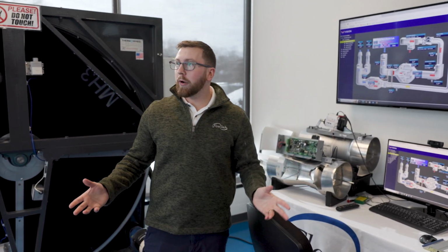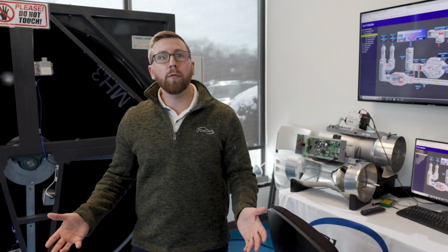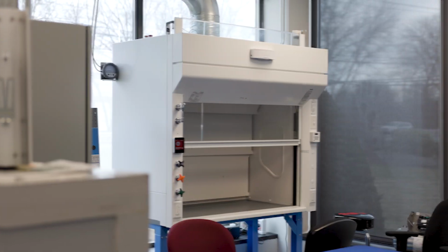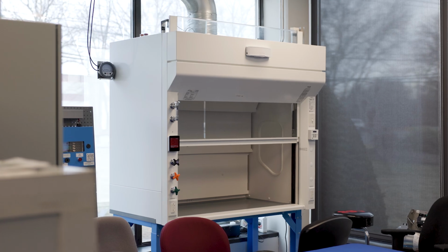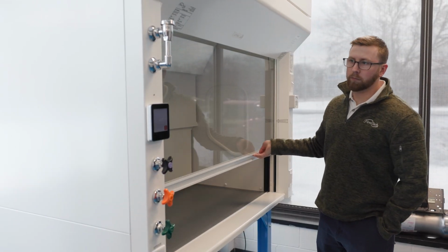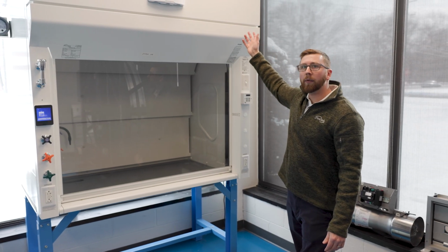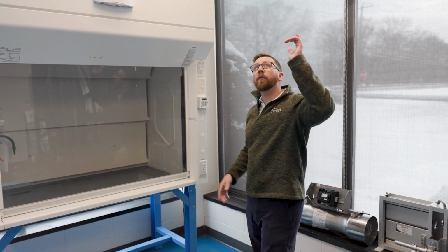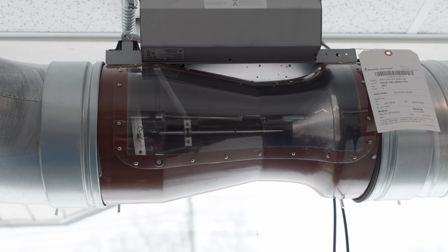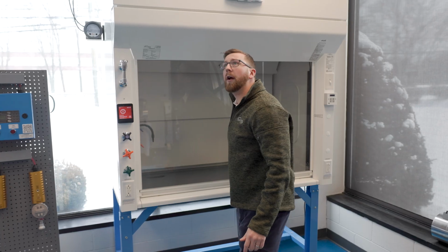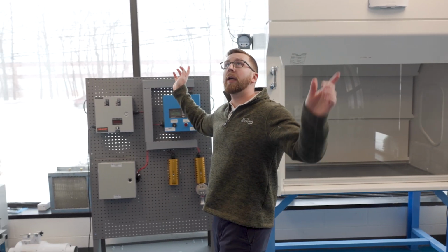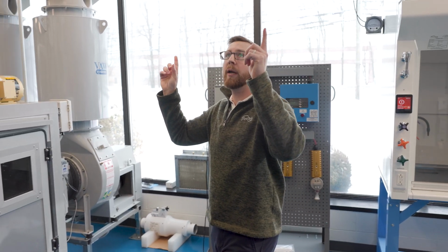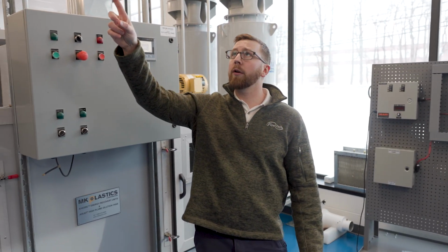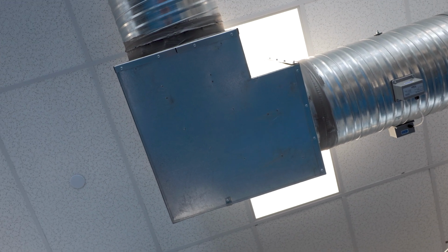So at this point, we are now in what we call the laboratory of the demo lab. The laboratory includes a fully working fume hood with fume hood display, zone presence sensor, and sash sensor. And the air either goes through our Phoenix general exhaust valve or the fume hood air valve if the fume hood is opened or closed. The air continues down the exhaust path where it mixes the general exhaust and fume hood air mix. We go through an elbow sound attenuator made by VAW, which also dampens the noise.